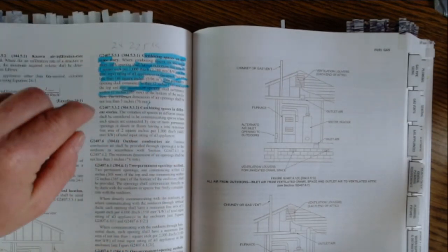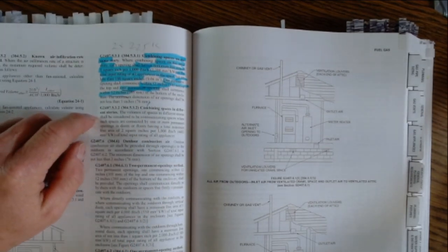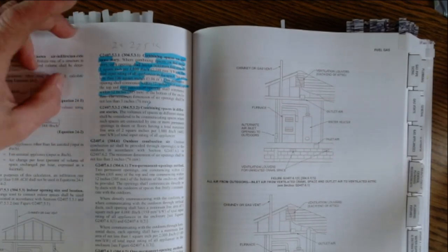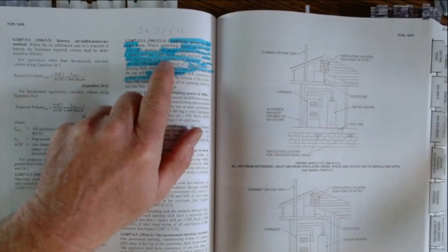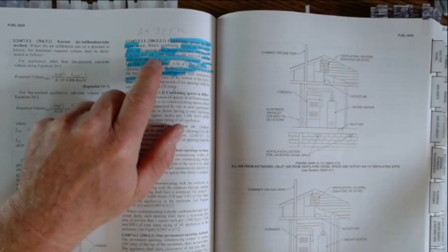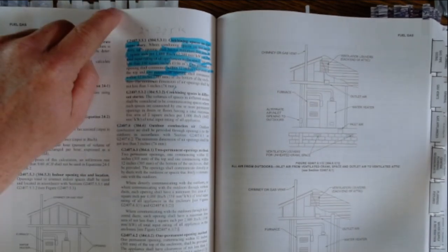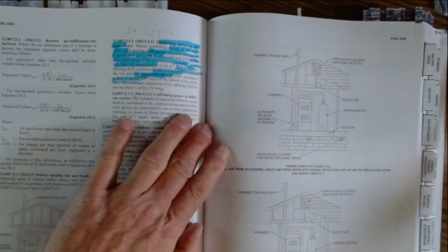So you're going to know this section here, and it's 1 square inch per 1,000 BTU, but it's top and bottom. Okay, so let's say a minimum 10-inch by 10-inch at the top of a room. We're talking rooms here, okay? You have opening top, bottom. It's minimum 10 by 10 here, 10 by 10 here. Even though it says 1 square inch per 1,000 BTU, it's actually 2 square inches per 1,000 BTU because 1 square inch is at the top, one's at the bottom. That's what these mean.